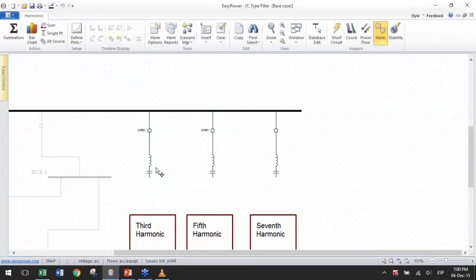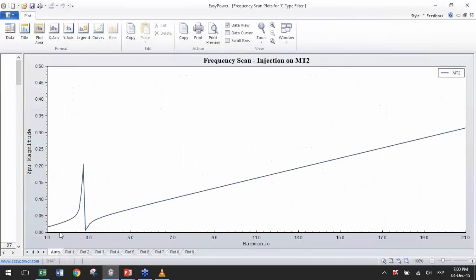Now, when I try and apply that solution to the third harmonic, let's say, I have a resonance right up at the second harmonic, which would normally not be a problem. But as I told you before, in an electric arc furnace, I have a lot of second harmonic. And if I leave this filter here, it will produce a lot of distortion in the voltage. So a notch filter, more than a solution, becomes a huge problem, because of this resonance that is behind the tuned frequency.